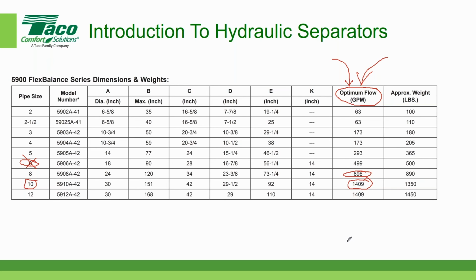Now, we do make standard sizes, as we said here, from 2-inch up to 12-inch. However, we can make hydraulic separators custom designed for much larger. And I have been out on job sites where the hydraulic separator has been as large as 36-inch pipe size connection. So we can make them quite large on a special order, but this is the information that's currently in our catalog for the 5900 Flex Balance and the Flex Balance Plus, same sizing chart.